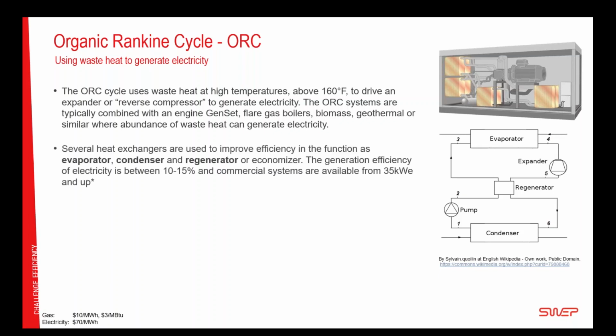There is a lot of need for heat exchangers, and typically brazed plate heat exchangers in ORC systems. You need them to evaporate, condense, and economize or regenerate the flows inside the system. I'm not going into details on how it works. We don't have time for that. But it's an interesting system. With all of this, it will take energy and transform it with about 10 to 15% efficiency. So it's not amazingly high, but again, if it's operating on waste heat, which is free, this is amazing. And commercial systems are available from 35 kilowatt electricity production and upwards. I'm using Electratherm by Bitzer as reference here.